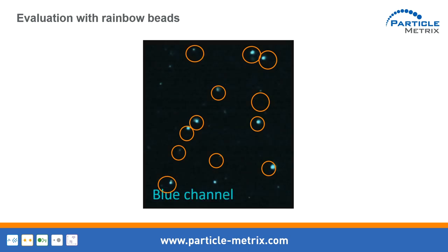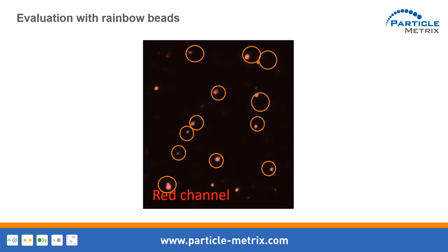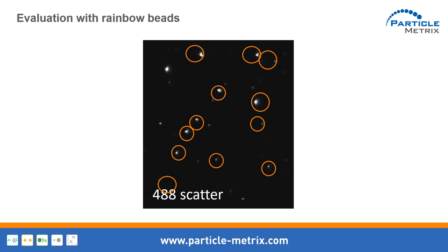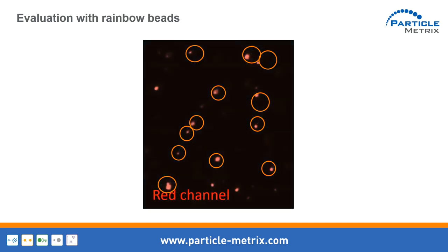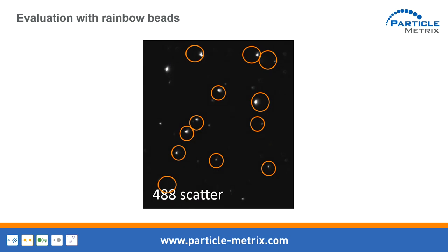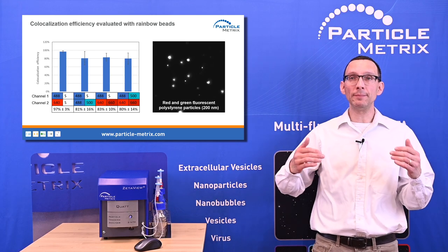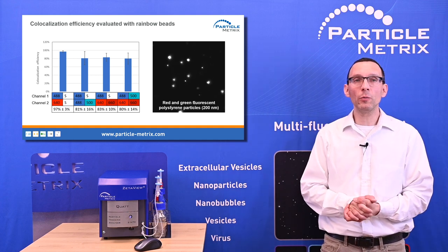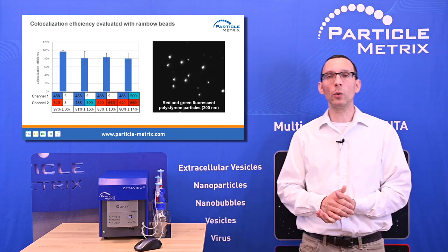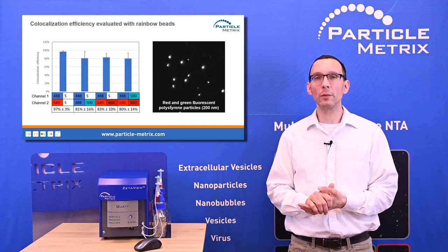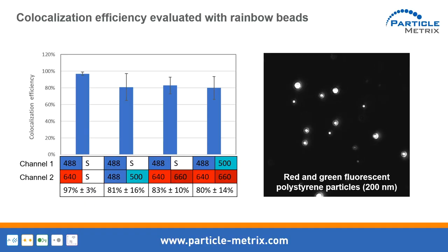The concentration must also be matched — if it is too high, artifacts appear in the linking. But at the typical measurement range of the instrument there is no problem, as the software detects such issues and calculates the co-localization efficiency. Evaluating the different modes — scatter-to-scatter, scatter-to-fluorescence, and the most challenging, fluorescence-to-fluorescence — we achieve more than 80 percent linking efficiency. Switching between lasers in scatter mode gives almost 100 percent co-localization efficiency, which is very encouraging.